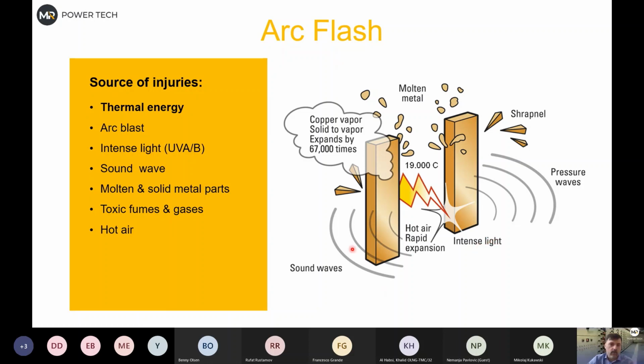So what else might you see? You might hear about the arc blast, because we have arc flash and arc blast. Blast, as the name suggests, is something that's going to hit you, which is pressure related. This would be a pressure wave generated by the expansion of gas inside, or generally by temperature in an enclosure. It has to be rapid, with very high short circuit current available for it, not a long time but very intense.